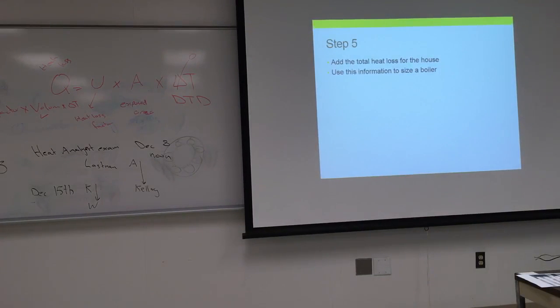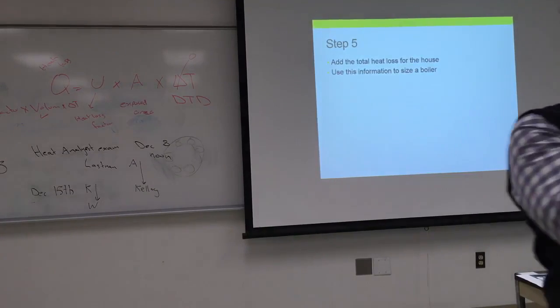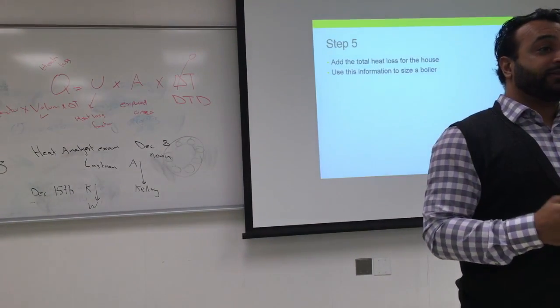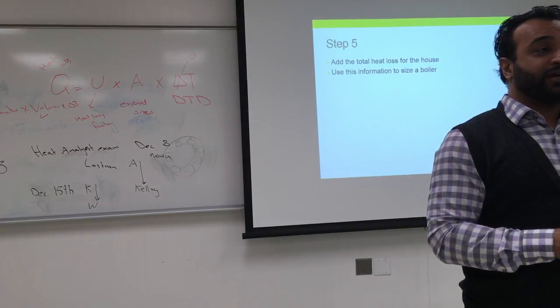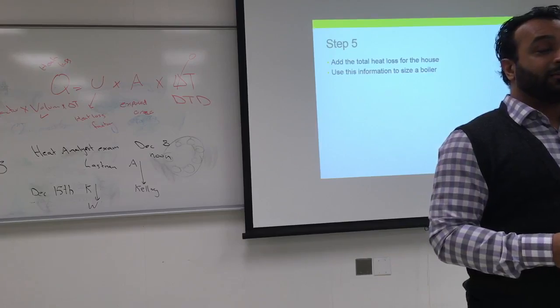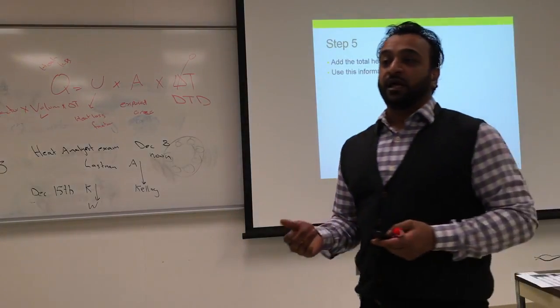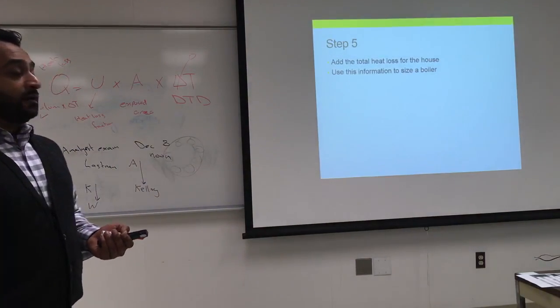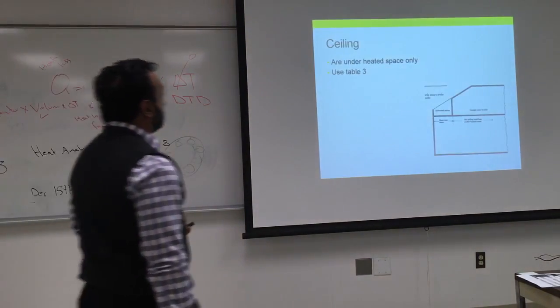Question: does that also work with a heat pump then? Yeah, you have 15% on top of the heat pump. Yeah, you have to. Otherwise, it's not going to heat up on cold days. It will work fine until one day the system goes out, you go on vacation, you put it down, you come back, and it takes forever to come back to the actual heat, and you might overwork the system a little bit. So that's how you size the boiler.